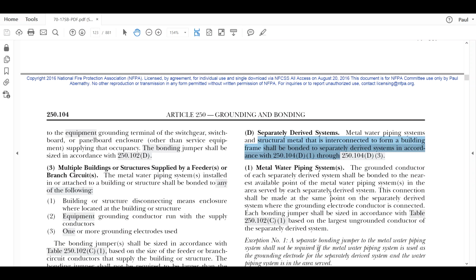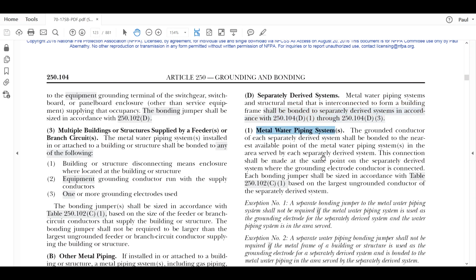Now we're going to look at D1 through D3. Now let's talk about the metal water piping. How do we do it? Okay, so we have a transformer. It's supplying a panel, and the panel is located in the area where this metal water piping is located. It says the grounded conductor of each separately derived system shall be bonded to the nearest available point on the metal water piping system in the area served by each separately derived system. Okay, so I have my transformer. It's serving a panel that's in this room, and the metal water piping system is in the area that's being served by this separately derived system. Okay, might be this side of the building or whatnot. It says the connection shall be made at the same point on the separately derived system where the grounding electrode conductor is connected.